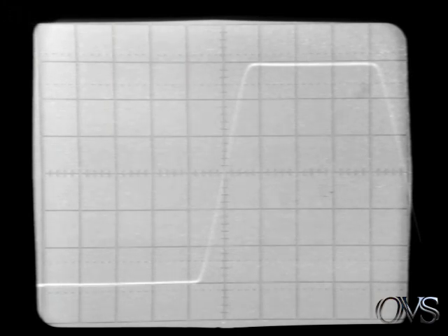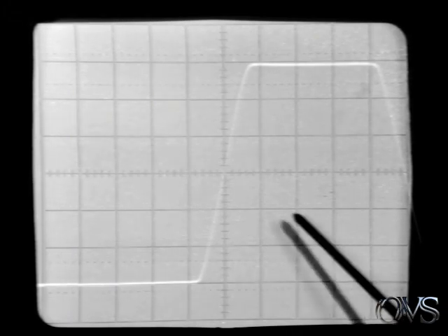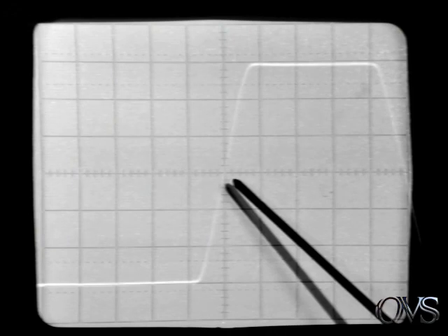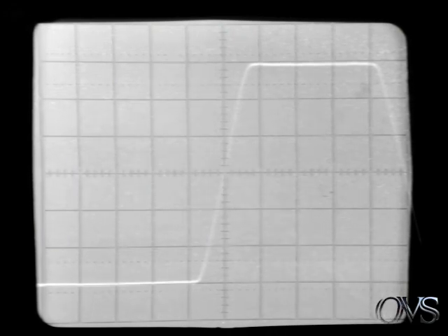Now, what we have really done to eliminate the inaccuracy of the CRT and the horizontal amplifier is simply to use the CRT as a nulling device. Remember, each time we took our measurements, that is, we measured the beginning and we measured the end of the delay interval, we referenced the waveform to the same location on the CRT. This tends to nullify the effect of the nonlinearity of the CRT and the horizontal amplifier. And so our accuracy now is simply the accuracy with which we can set the delay interval.